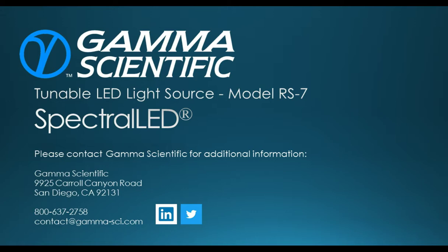Okay. How often does the equipment need calibration? So we're recommending a 1-year calibration cycle, which is basically to adhere to our NVLAP ISO 17025 accreditation. But within that 1 year, there's no limit on the number of hours that you can run the device. So unlike the tungsten halogen 100-hour lifetime or 1 year, in our case, you could run it continuously for the entire year and still have a very high confidence in the output power.